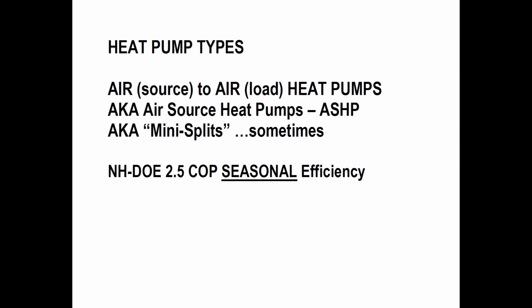I mentioned sources of energy. There are heat pumps that are called air source heat pumps. They should be referred to by the initials ASHP, air source heat pump. They get their source of energy from the air. Most people think of these things, oh, you mean a mini split? Yeah, a mini split, that in most people's mind is something that hangs on the wall, which is what Rick and Ann have now, with something outside, and it blows heating or cooling air into the space. And that's your standard mini split.